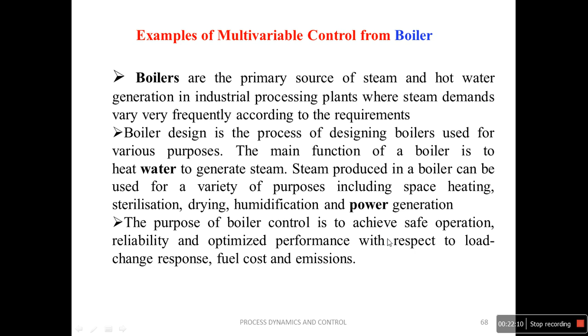The purpose of boiler control is to achieve safe operation, reliability, and optimized performance with respect to load change response, fuel cost and emissions. Even with load variations and load changes, we have to get a control that achieves safe operation. What is safe? I will discuss. If you are not able to control the level of the boiler to a proper level, what happens? That leads to damage of some boiler tubes. So the main purpose of our boiler control is to achieve safe operation, reliability and optimized performance.